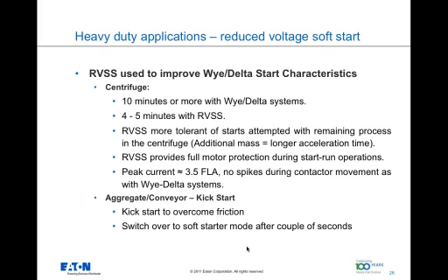And also the peak inrush that is dictated by the soft starter is roughly 3 to 3.5 times FLA, whereas the typical wye-delta system draws a continuous 5 times FLA for an extended period of time.